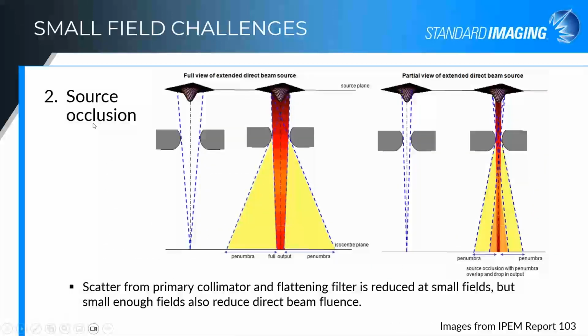The second point on my list is source occlusion. And these images come straight out of that IPEM report book that I cited at the beginning, where as you have your jaws out for larger fields, this full, usually Gaussian type shape of the source of the beam where the x-rays are being generated within the target, it is seen by a detector here along the central axis. As you collimate inwards, you can see the illustration shows that primary source coming from direct view between your detector and the beam source.